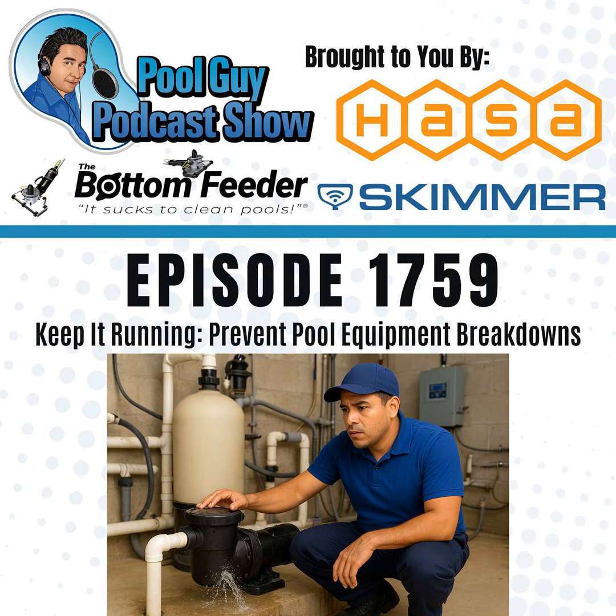Now, you may hear that with the variable speed pump, but that's really not the bearings going out. When it's really cold out, 40 degrees out or 50 degrees out, those things have some trouble when it's cold, and you're going to hear that similar noise as if the bearings are going out, but once it warms up and starts running for a few minutes, that noise goes away. And by the way, a single speed pump, when the bearings are going out, sometimes the noise will go away once it starts warming up and getting hot, and that's something that happens once in a while.